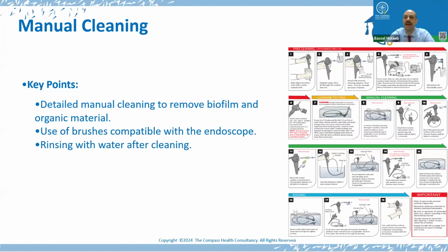And the area where the manual cleaning of the scopes occurs must have the optimal lighting and magnification and additional aiding tools to ensure that the lumens and all the surfaces of the scope are being checked properly. So in that process, in the manual cleaning, the sink that is designated for scope cleaning is filled with the detergent that is compatible with the endoscope as per the IFUs.